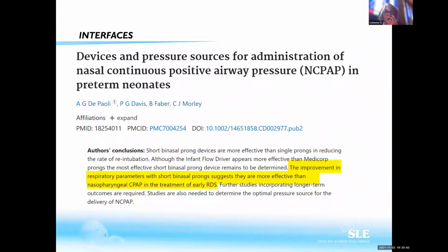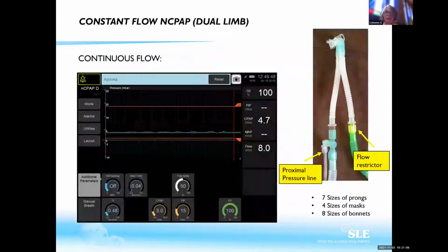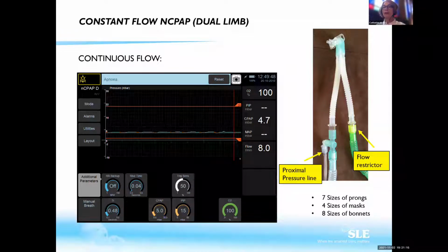Okay, so which interface should you use? There are a few studies which support the use of short binasal prongs, where it seems that you are better able to transmit the pressure. You have less pressure loss in the interfaces, and you can also have a good seal whenever you deliver the CPAP. Whenever you use a CPAP, you actually have two types. The first one that you might have in your ventilator is what we call a continuous flow CPAP. So what is this one?